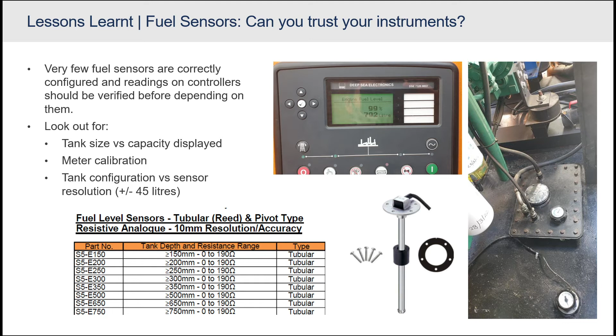On these fuel sensors, when you look at the data sheet, they will stipulate the resolution or the accuracy. This one, for instance, is a very common one that we find in the field, and it's got a 10 millimeter resolution. The reason it's a problem, and you would rather go for at least a 5 millimeter resolution, is that these tanks are normally big flat tanks with the generator placed on top of them, which means 10 millimeters in such a big area can equate to close to 50 liters. So your accuracy at best is normally close to 50 liters. That is normally the biggest issue.